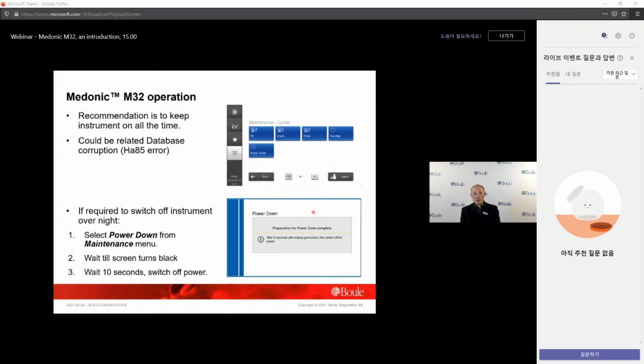After the user confirms they would like to power down, a message shows up: wait 10 seconds after the display goes blank. So the user really needs to see the screen turn black, wait 10 seconds, and then switch off. It is pretty simple and pretty obvious, but in some cases the instrument technical files indicate the instrument was powered off suddenly while the database was still open. So we would like to put some extra emphasis on this.